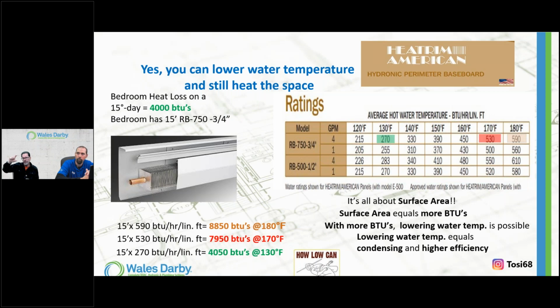This is a baseboard spec sheet, a chart showing you it's not just 180. Again, they give you that 590 at 180. That's great, but that doesn't mean I get nothing else when I do 150, 140. So I did the math here, and you can see in green, using 130-degree water with 15 feet of baseboard, I'm still producing over 4,000 BTUs for a 15-degree design day. I only need 4,000 when it's 15 degrees out. What do I need when it's 35 out, though? Halfway between 0 and 70 is 35.